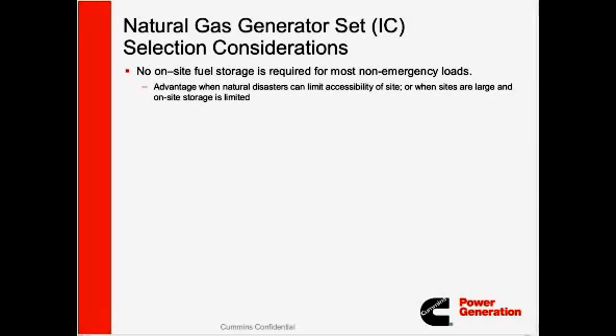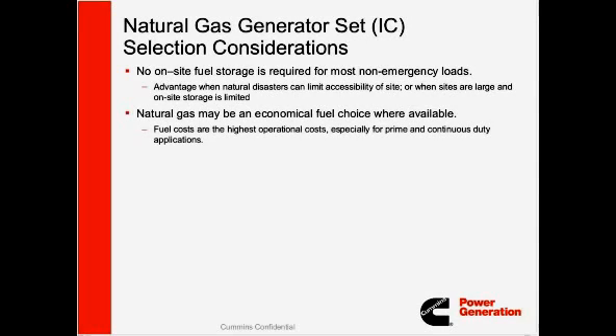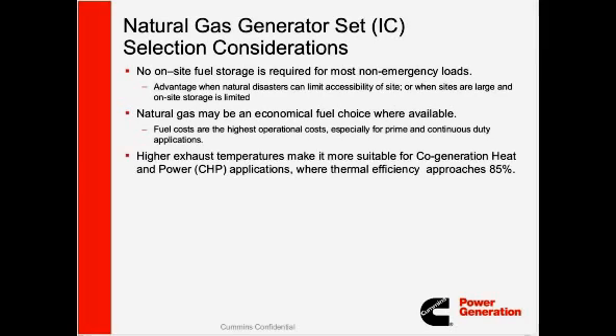The fuel costs are the highest operational costs, especially for prime and continuous duty applications, and that's why you see natural gas gensets used for many base loading type applications and combined heat and power type applications. Higher exhaust temperature make it more suitable for cogeneration or combined heat and power applications because the thermal efficiency can approach up to 85 or 90%. And this is used mainly, increasingly with the Smart Grid Initiative and Renewable Energy Initiatives, and we'll talk about that later.